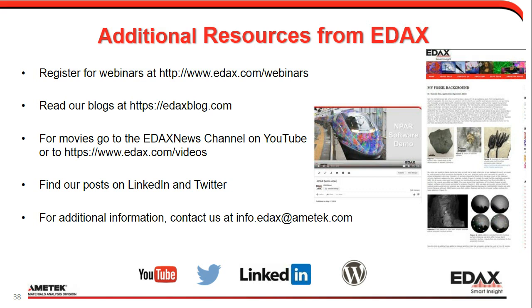Question of hardware limitations for dual detector configurations. Yes, there is. First of all, your microscope should be able to fit two detectors. Some of the smaller microscopes, you will only have space to add one EDS detector on there. Even some of the bigger ones, depending on how much other stuff you have mounted. But it's primarily which ports are available on the microscope. There are some microscopes where that can give us a bit of additional complications if the ports are not at the same angle.